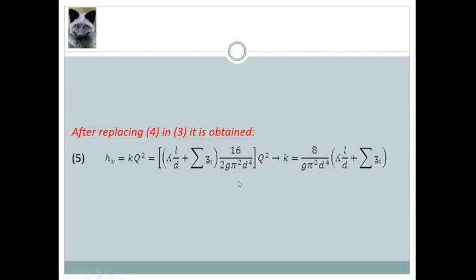Equation 5 represents the option in general for estimating the coefficient K of a simple pipe system resistance curve. However, it must be taken into account that sometimes it has to be modified so that the Coriolis coefficient alpha is involved.